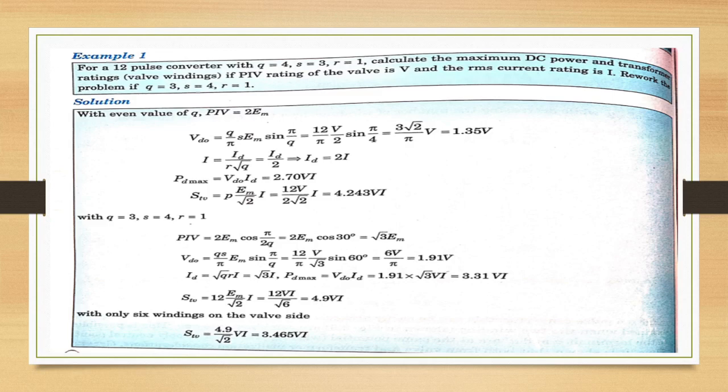For a 12-pulse converter, in HVDC transmission, series connection of converter groups is preferred because of the ease of control and protection as well as the requirements of high voltage rating. So a 12-pulse converter is obtained by the series connection of 2 bridges. A 30 degrees phase displacement between the 2 sets of source voltages is achieved by the transformer connections: star for feeding one bridge and star-delta for feeding the second bridge. The use of a 12-pulse converter is preferable over a 6-pulse converter because of the reduced filtering requirements. However, increasing the pulse number beyond 12 is not practical because non-characteristic harmonics will not be eliminated.